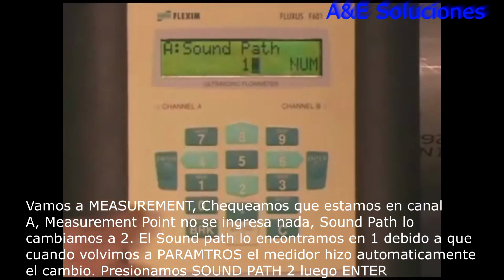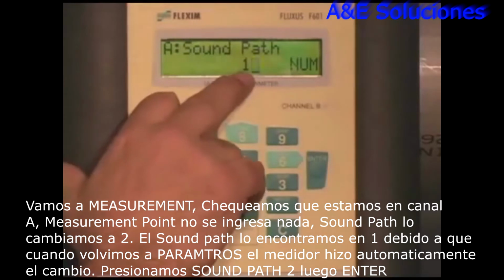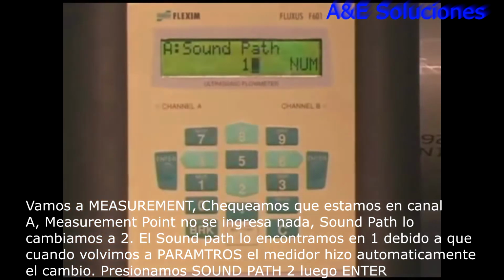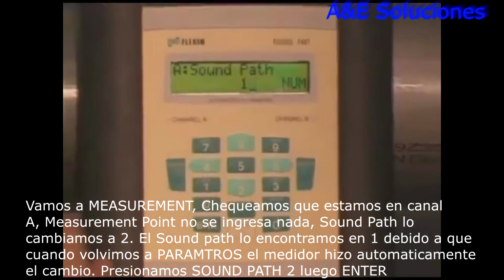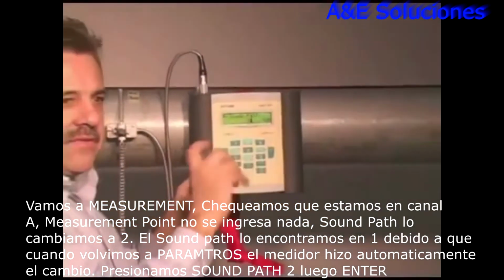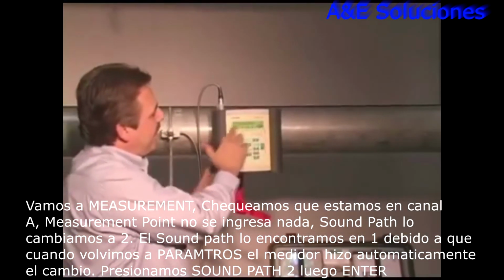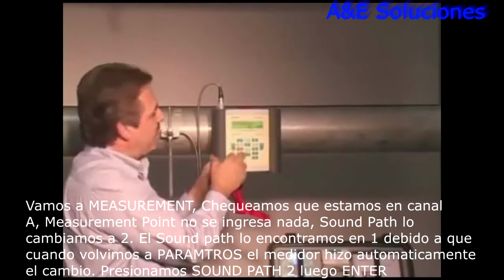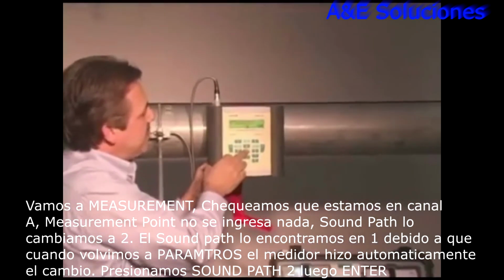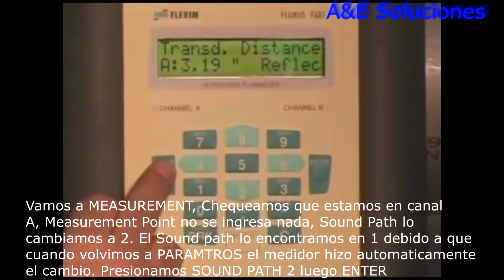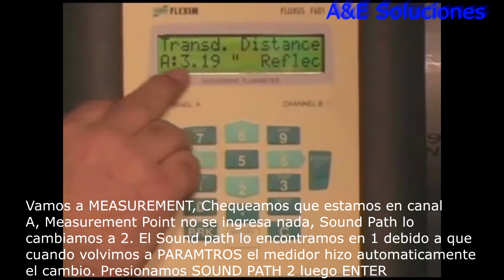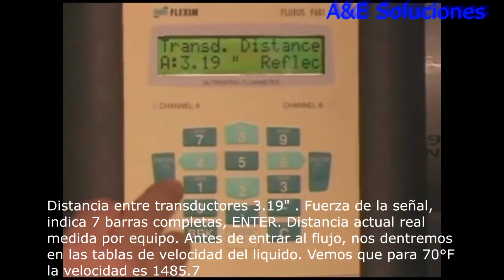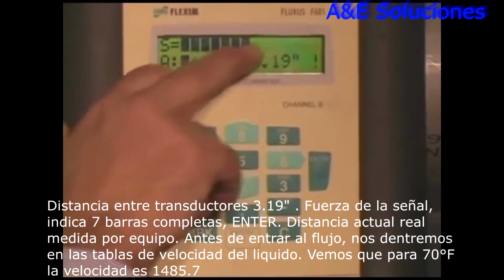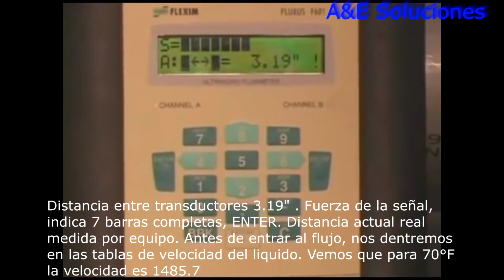Number of sound paths, I'm going to change that to 2. Now you'll see that it defaulted itself back to 1. That's because I went over to the parameters menu and it caused this to go back into a default state. Okay, so I'm going to hit the 2 sound paths, enter. And it gives me the spacing distance, 3.19 inches, enter. My signal strength, lots of bars of signal, enter.